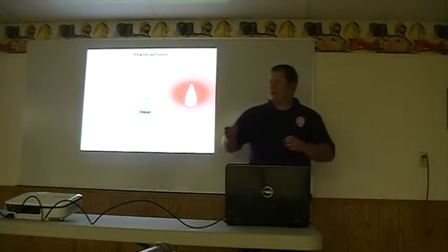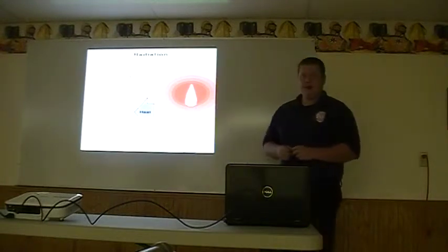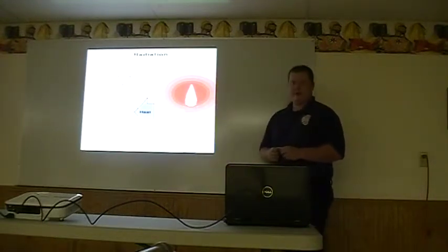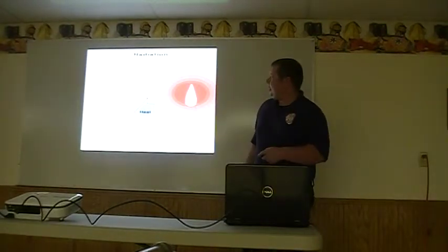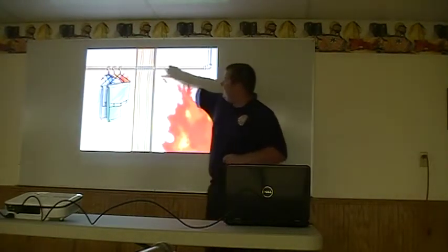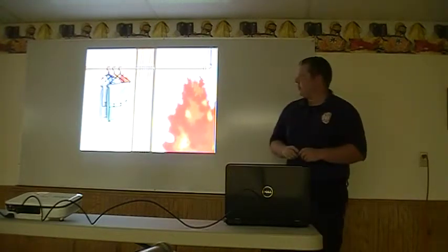So we're going to talk a little bit about thermal imagers. Radiant heat is the only heat that a thermal imager can see. It cannot see hot air, and it cannot see heat moving through an object. It can only see the radiant heat coming off of the object.